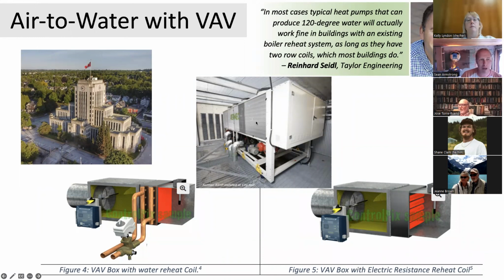This is an Aermec heat pump. This is the Vancouver City Hall installation. They craned it in. And this is one of our leading engineers in the state saying, in most cases, typical heat pumps that can produce 120-degree water, which is all of them, will actually work fine in buildings with an existing gas boiler reheat system, as long as they have 2 row coils, which most buildings do.